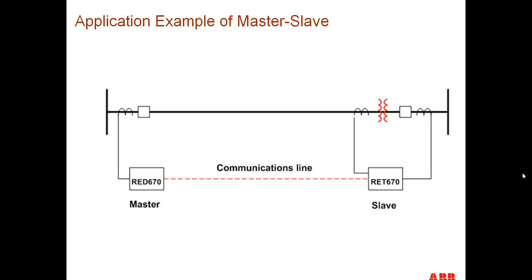When you're using a line current differential, all of those schemes are used so that you can get 100% line coverage on a line distance relay, because you normally don't set the zone 1 relay past 80%. That last 20% you have to cover somehow, and that's what the communications for the permissive overreaching and permissive underreaching schemes are used for. You're already covering 100% of the line section with the line current differential, so you don't need any auxiliary logic in the relay to do that.